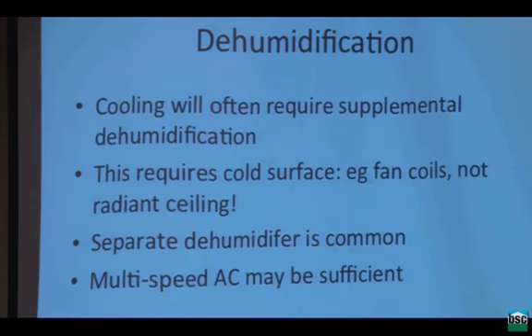But when you get to low load buildings, the equipment is just not available that's small, efficient, and affordable. And so you have to kludge something together, and for custom homes you can do it, usually not worth it. Separate dehumidifier is a common requirement. As I said this morning, I'm not quite willing to say every low-load house has to have a dehumidifier if it's air conditioning, but I'm pretty close to saying that. Because I really think that if you're east of the Mississippi, 90% of low-load houses are going to need supplemental dehumidification of some type or tolerate higher humidities and higher temperatures, some combination of that.